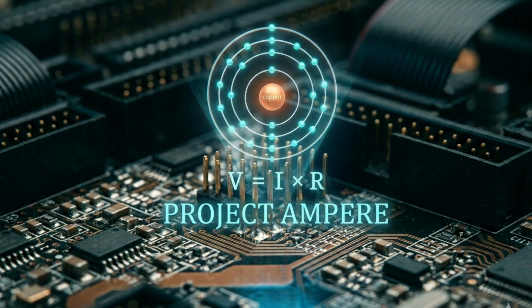For the first few milliseconds, typically 10 to 50 milliseconds, that 5-amp light bulb isn't drawing 5 amps. It is drawing inrush current. How high does that go? That inrush can be 15 to 20 times the operating current. Wait, so 15 times 5. We are talking 75 amps.